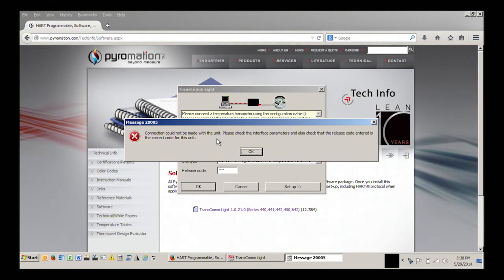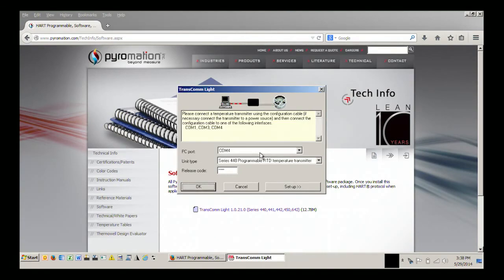Connection cannot be made with unit. Please check the interface parameters and also check that the release code entered is the correct code for this unit. The release code would be the password that could have been programmed in to lock someone out from changing the unit. The default code is the reverse of the transmitter type, 044 for the 440 transmitter.